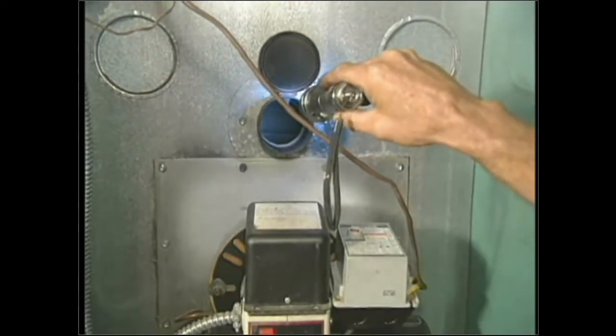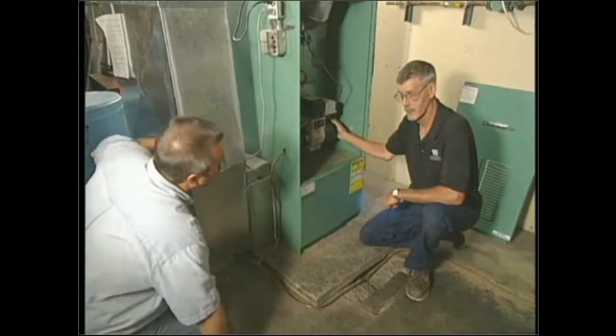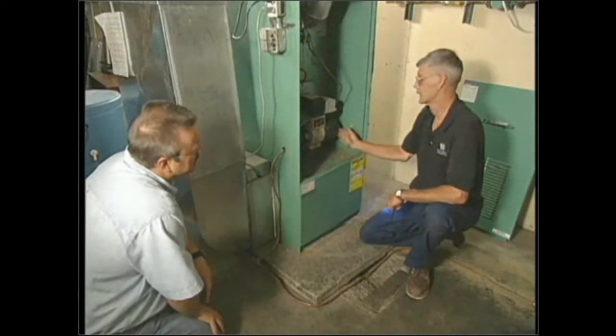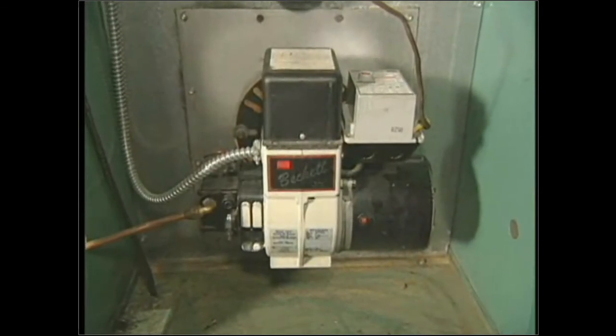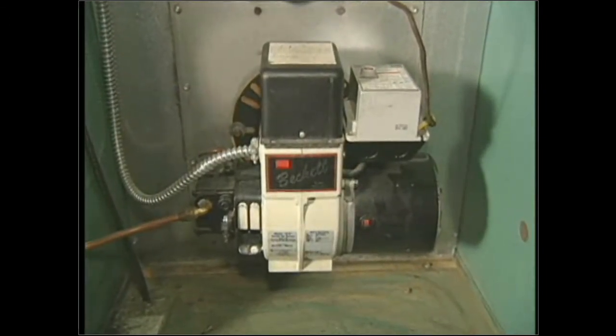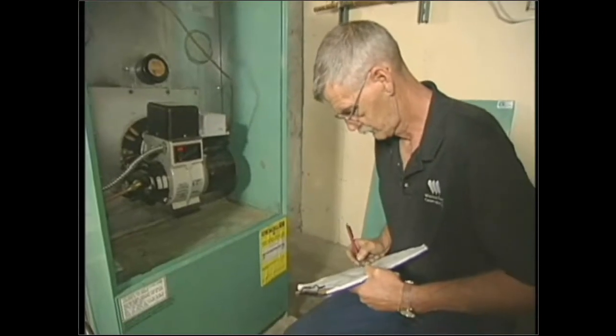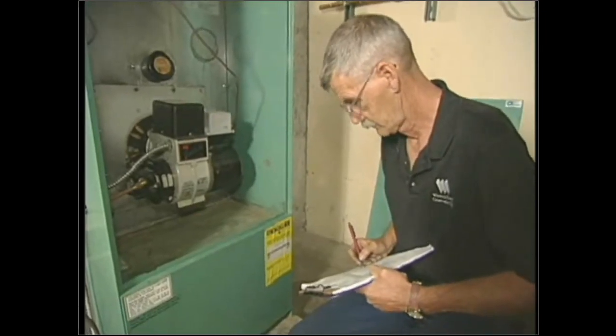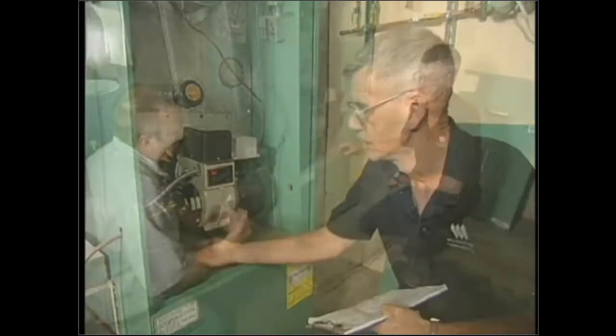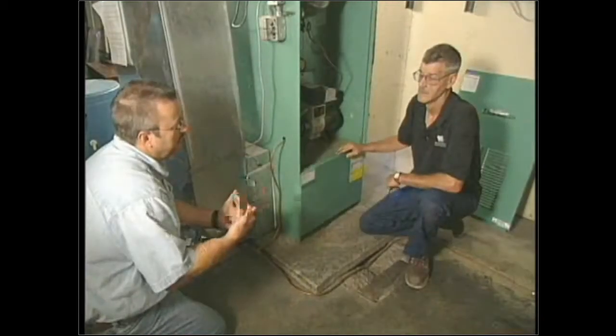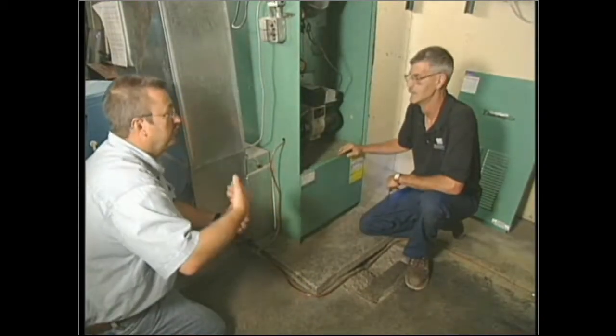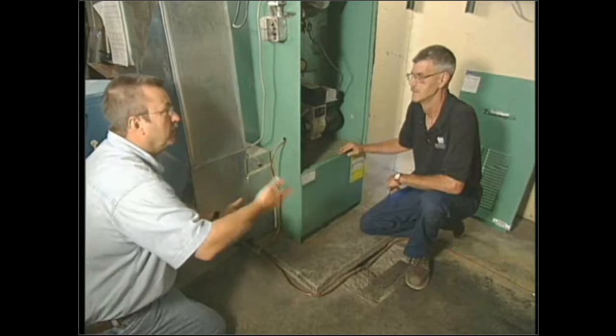Yep. We'll take a look at this burner motor. What we're looking for is to see if this is an oilable type or not, if there's air ports that need to be cleaned, if it's sound. The auditor should make sure that he documents all this, because if this is an oiled one, we want to make sure it gets oiled. And again, all this documentation is so the auditor can convey their findings to the contractor, and then you can double check it once the job is done when you come back.